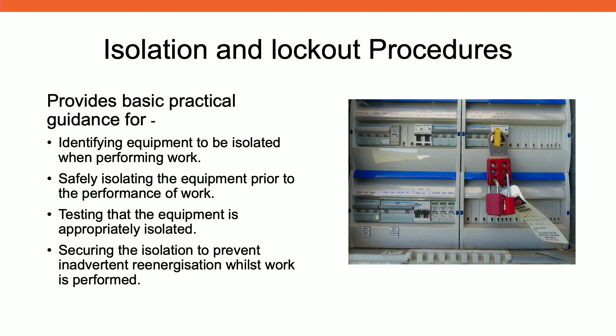There's another book that covers isolation and lockout procedures. This provides basic guidance on identifying the equipment that you're going to work on. We've had incidents before where the equipment is misidentified. Then safely isolating that equipment by various methods. Testing that the equipment is isolated is critical. And if we go back to the energised work, the testing to ensure that it's de-energised is energised work and must be done in a safe way as if the equipment was energised.